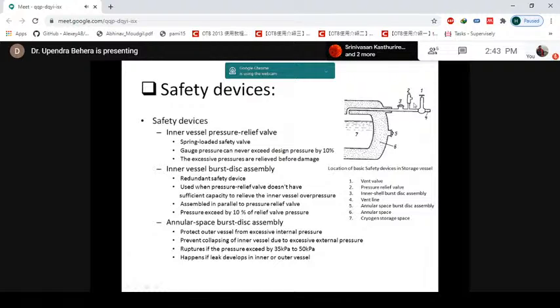This is in addition, for redundancy. They have put this bursting disc for the inner cell so that it should not, at any time, burst. Okay, so what happens in this is the safety valve is generally a spring-loaded safety valve, and this gauge pressure cannot exceed the design pressure by 10%. So these are all spring-loaded, and the spring load is adjusted so that when the pressure inside the container is more than 10% of the design pressure, this safety valve should open the seating so that this high pressure vapor is relieved. And once this pressure comes down below the set value of this valve, it will sit back and close so that there won't be any vent going out, keeping the container safe.